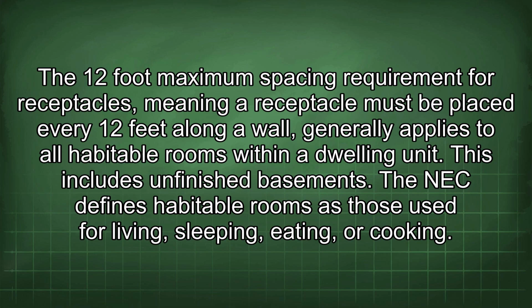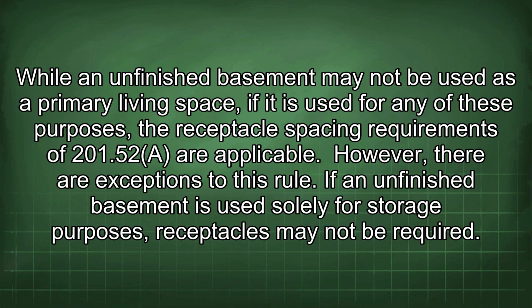The 12-foot maximum spacing requirement for receptacles, meaning a receptacle must be placed every 12 feet along a wall, generally applies to all habitable rooms within a dwelling unit. This includes unfinished basements. The NEC defines habitable rooms as those used for living, sleeping, eating, or cooking. While an unfinished basement may not be used as a primary living space, if it is used for any of these purposes, the receptacle spacing requirements of 210.52(A) are applicable.